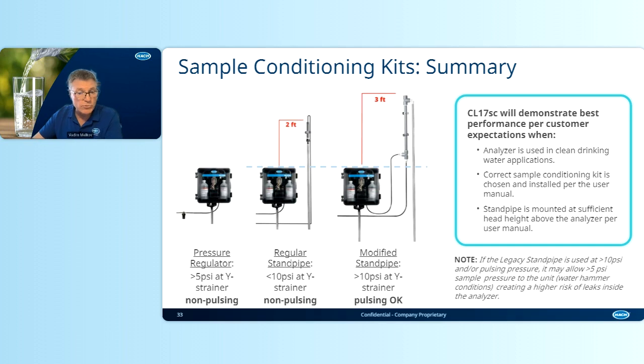And this is how you really take care of it. You need to use, of course, the analyzer in the intended applications. Yes, that's when it will demonstrate the best performance and meet the expectations. The correct sample conditioning kit should be chosen, and the standpipe, if it's chosen, must be mounted as required.